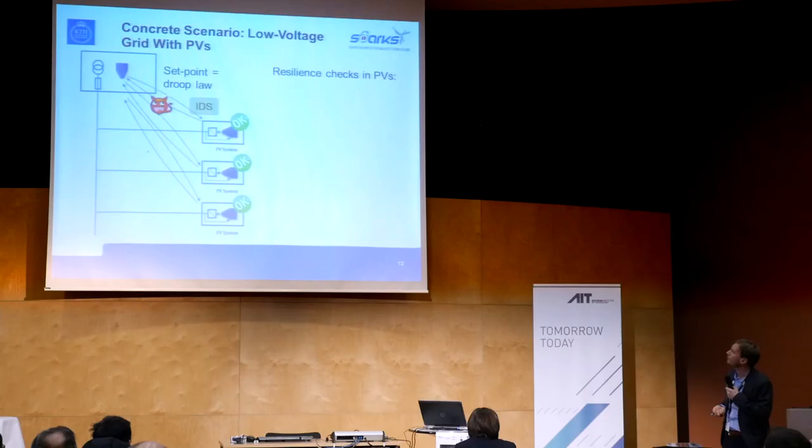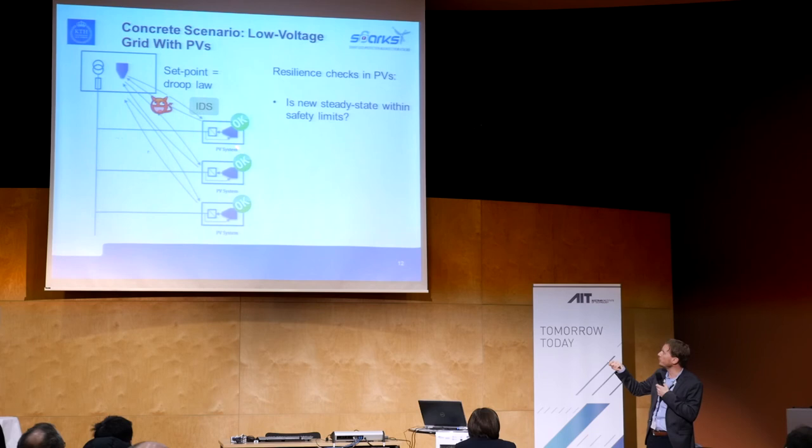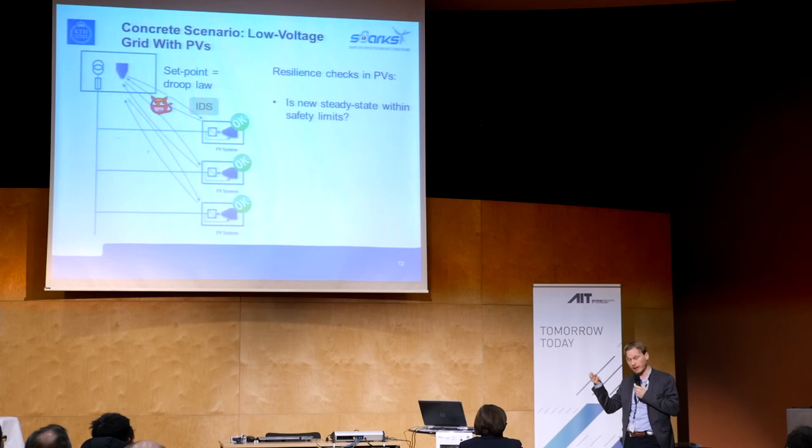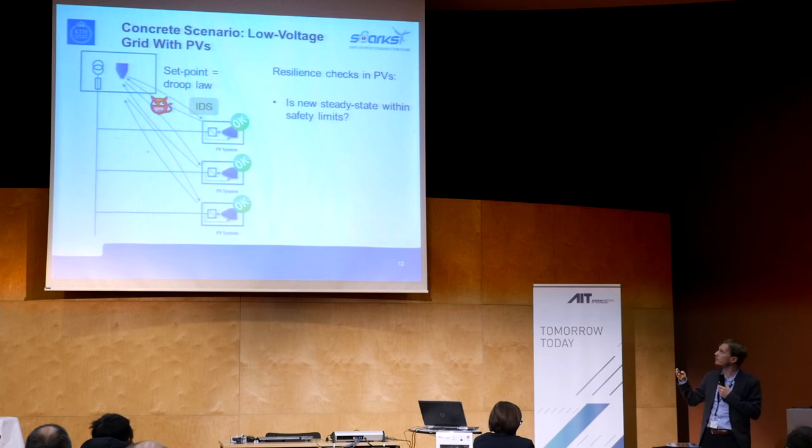What type of checks do we do in the PV system? First, we assume the PV systems have some sort of anti-islanding controller that estimates the grid impedance. Using that impedance, it can predict: if I execute the command I received, what is the new steady-state voltage I should reach? If that predicted voltage is outside acceptable limits, maybe I shouldn't execute this command — or at least I should send a warning. That's the first simple, completely decentralized test you can do locally.